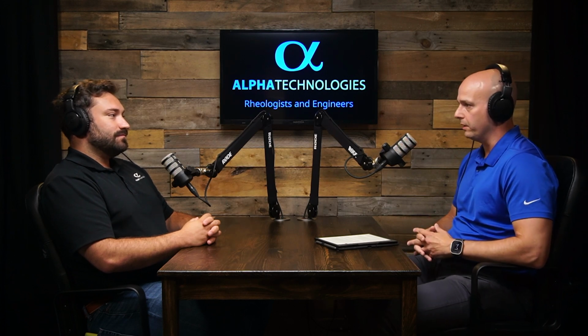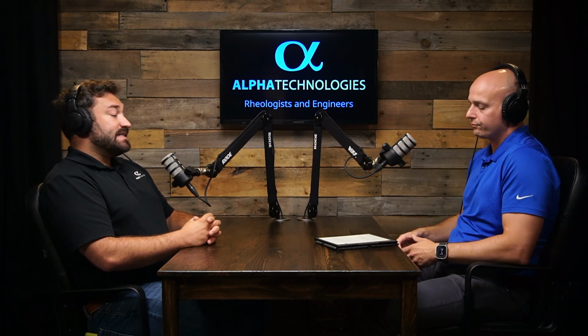So what is LAOS? It sounds complicated, but the good news is all the complicated stuff is behind the scenes. Our software engineers at Alpha Technologies have basically done all of the math for you. And this is a new way of testing materials. Typically, RPA or MDR testing is done around 1% or less strain. So that's where the large amplitude comes in here. We're going to be dealing with 500%, maybe 1,000% strain.